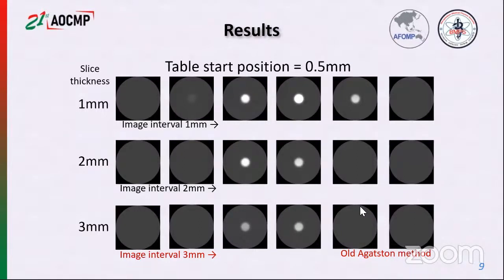This is a result image. In this table, the start position is 0.5 mm, and the slice thickness was changed to 1 mm, 2 mm, and 3 mm. The 3 mm slice thickness is the old Agatston method.